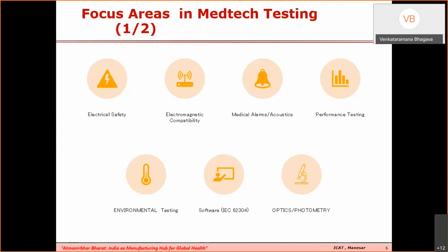The next category is software. As you know, every device has some sort of software nowadays. Here again, the crucial aspect to consider is that there should be no harm to the patient due to software failures. So the software is divided into different risk classes such as A, B, C, and so on, and then evaluated. The procedure is similar to regular software testing and validation, such as unit level testing, system level testing, integration level testing, and so on. But this process is customized for the medical device environment. And next, we have certain optics tests if the device has some optical components.